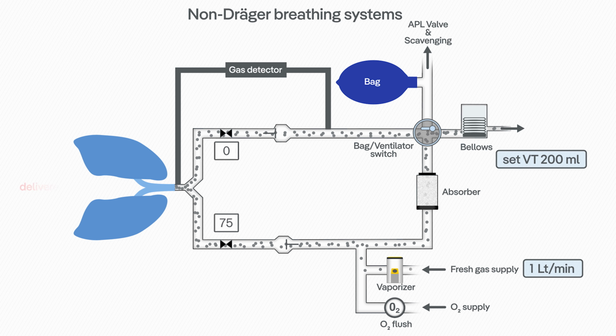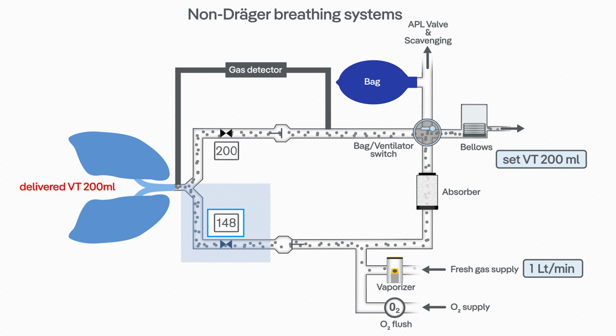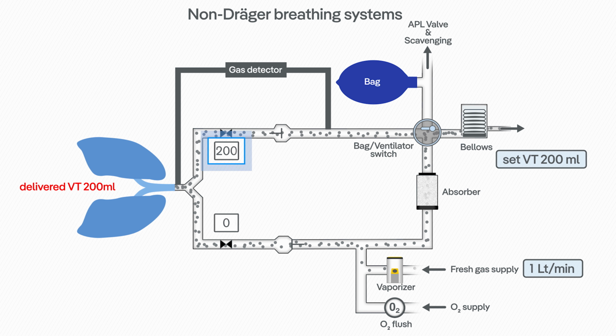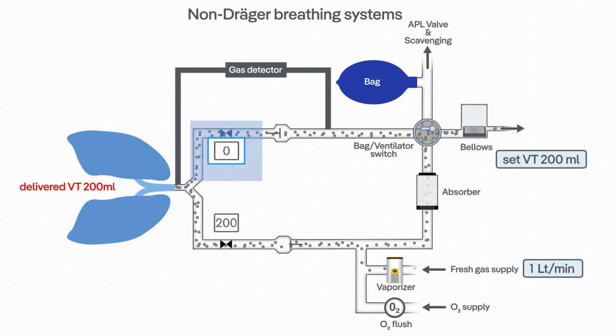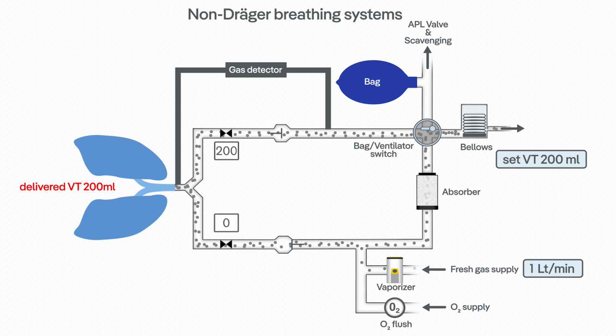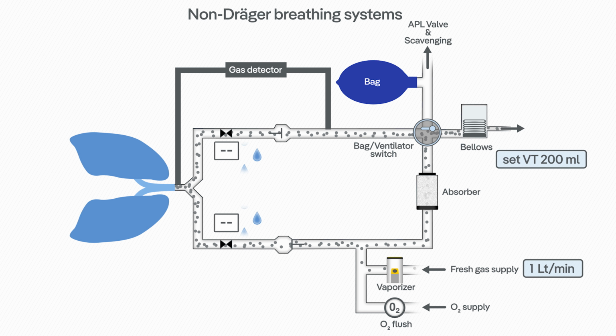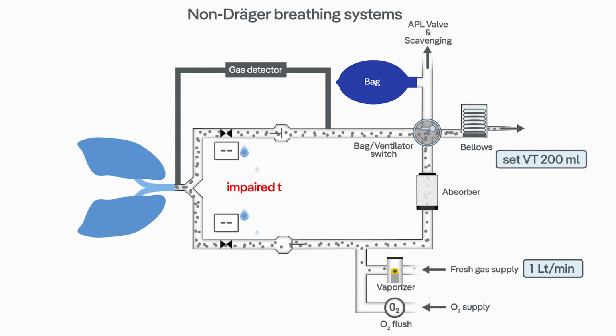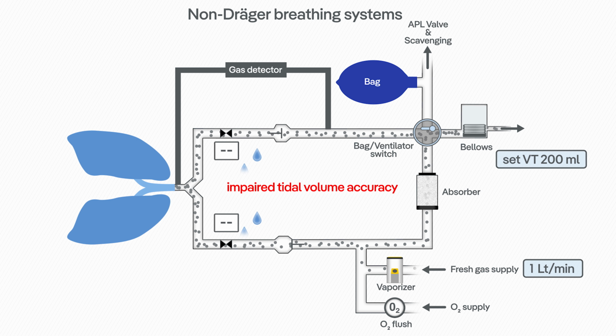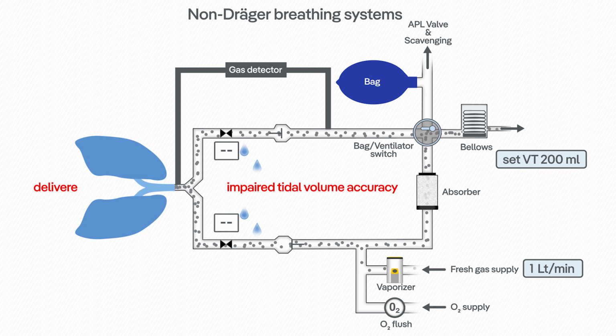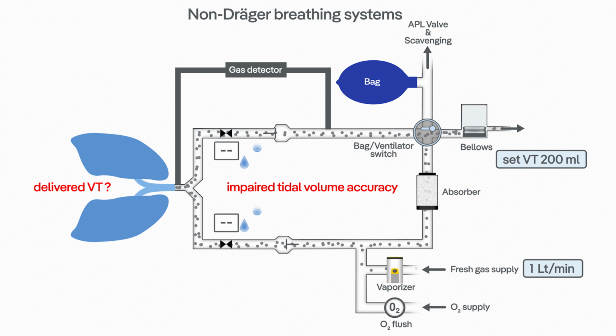Flow sensor measurements are used to calculate the tidal volume delivered to and being expired by the patient. Thus, a high precision of flow measurement is crucial for exact tidal volume delivery. Depending on the technology used, condensation can impair precise measurement of flow sensors. Ventilators that are depending on this measurement will not be able to perform accurate tidal volume delivery.